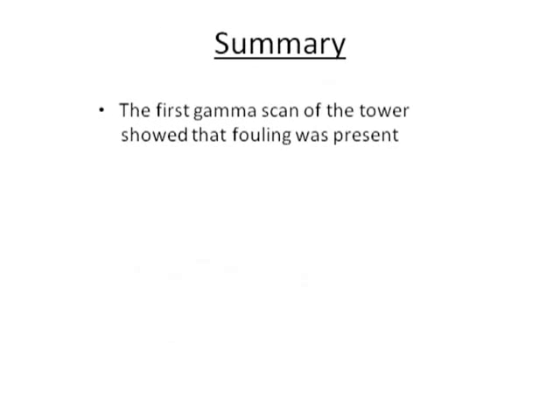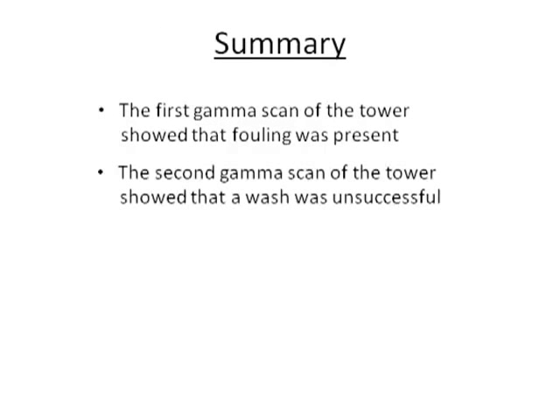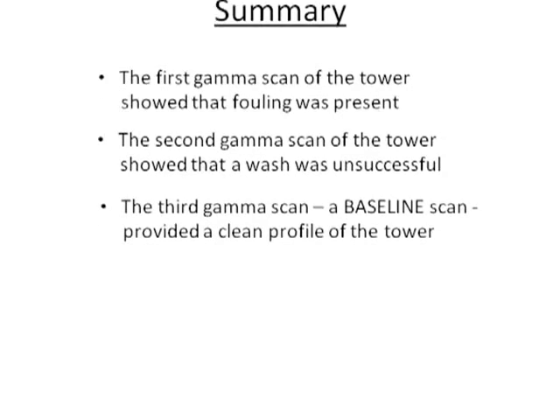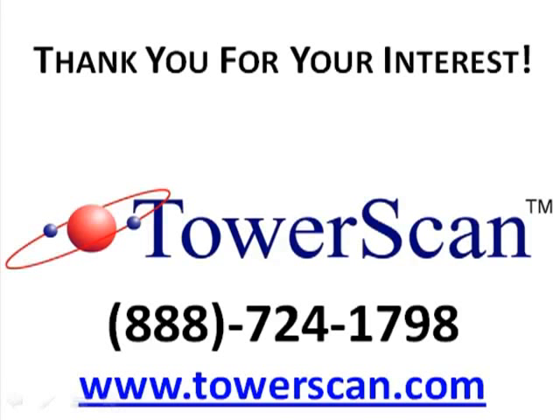To summarize the results, the first gamma scan of the tower showed that fouling was present. The second gamma scan of the tower showed that a wash was unsuccessful. And finally, the third gamma scan, a baseline scan, provided a clean profile of the tower for future troubleshooting. Thank you for your interest.